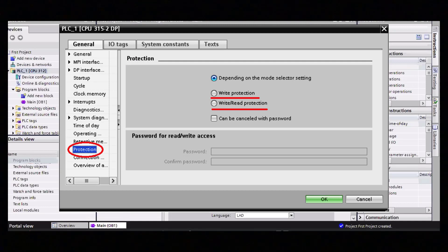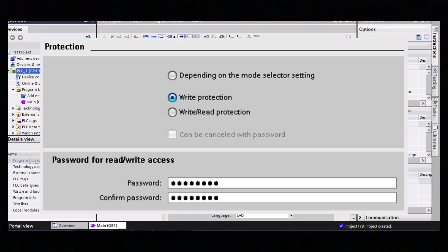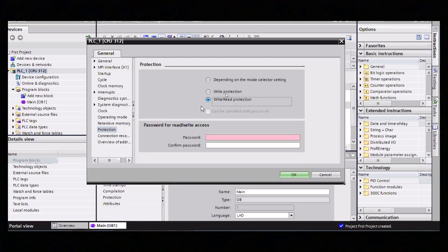Let me explain what Write Protection is and what Write and Read Protection is. In Write Protection, we can create a password for downloading the PLC program. Whenever someone tries to download the program into the PLC, it will ask for the password — only an authorized person who knows the password will be able to access the PLC. The second option is Write and Read Protection. By using this option, we can protect our PLC program and set a password for both uploading and downloading of the PLC program.